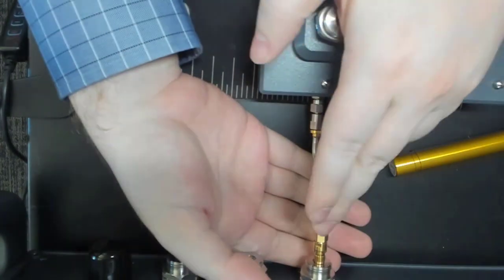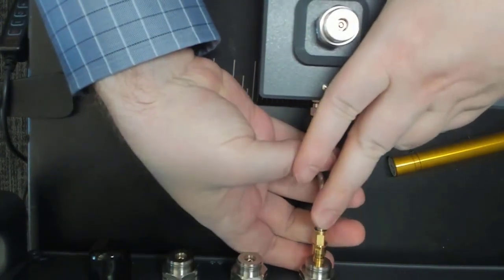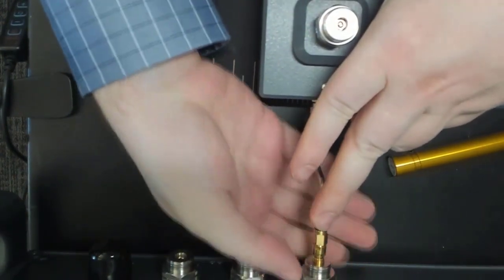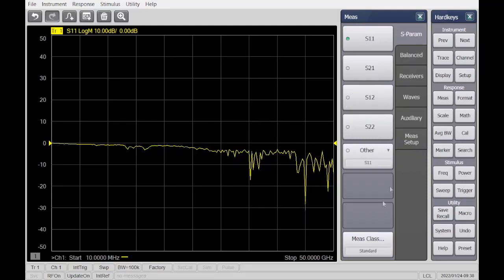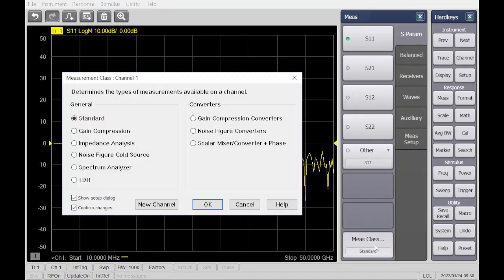Attach the adapter box to the VNA port 1 via the rigid cable. On the ENA, change the measurement class to Impedance Analyzer and select the desired stimulus settings.